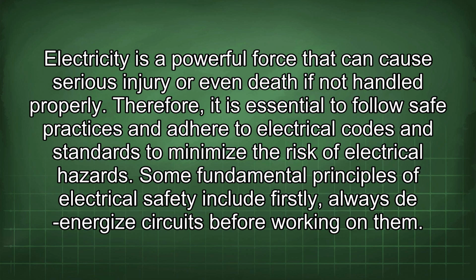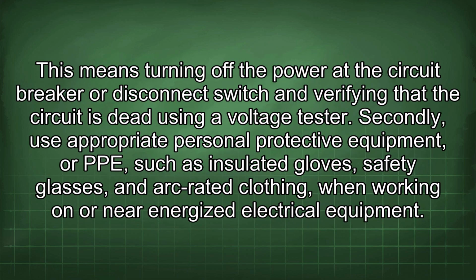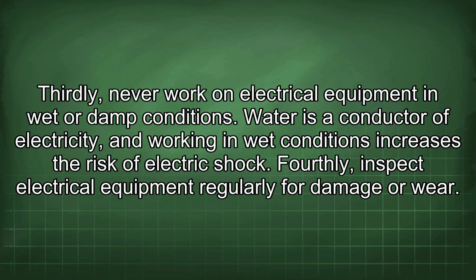Some fundamental principles of electrical safety include, firstly, always de-energize circuits before working on them. This means turning off the power at the circuit breaker or disconnect switch and verifying that the circuit is dead using a voltage tester. Secondly, use appropriate personal protective equipment, or PPE, such as insulated gloves, safety glasses, and arc-rated clothing when working on or near energized electrical equipment. Thirdly, never work on electrical equipment in wet or damp conditions. Water is a conductor of electricity, and working in wet conditions increases the risk of electric shock.